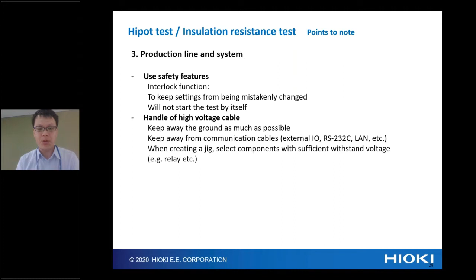So these are our Hipot tester and insulation resistance tester from Hioki. We have 5 kinds of product. We have the 3158. This is an AC Hipot test only. We also have the 3159. The 3159 can do the AC Hipot test and insulation resistance test. You can do both. And we also have the 3153. This is an all-in-one type. It means you can do the AC DC Hipot test and the insulation resistance test. In addition, it has an auto test function and a scanner. If you want multiple points for Hipot test and insulation test, we strongly recommend using the 3153 and our scanner.